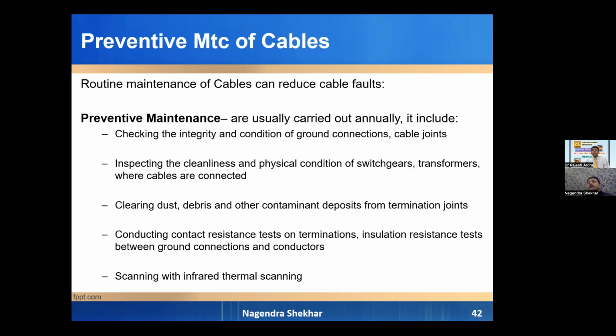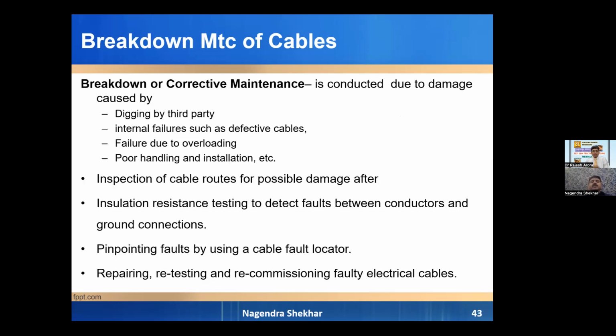Many a time a cable fails in case of a fault, and current does not flow through the earth, but from some point which is far distant from the switchgear. For contact resistance, we have to ensure it, and we have to conduct an insulation resistance test between ground and conductors, so that the insulation resistance is proper.